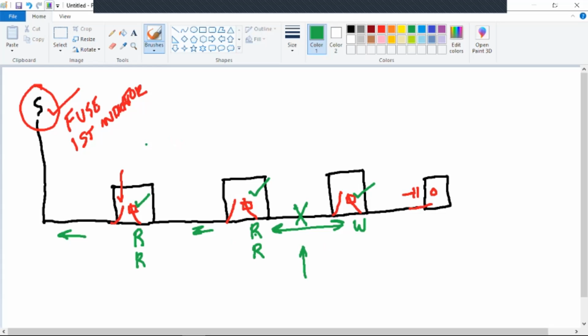Right. Right? And high potting would just make sure that you had the bad span and your indicators did work correctly. Now, I've drawn a simple 1, 2, 3 transformer span. You're going to get in subdivisions in some projects that have 20, 25 transformers in a span. Right. So you can see if I'm able to drive by this one, come to this one, up, found it in a 25 transformer span, well, you're saving a ton of time. Mm-hmm. Okay. All right. So I'm going to go one more thing here. I'm going to say this is transformer 2 and transformer 3 that we saw before. So I'm just going to draw those two.